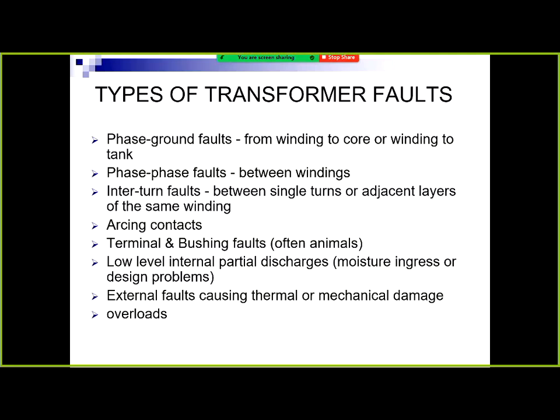So that would be arcing contacts. It's just sometimes you get a bad batch of contacts. I've heard that, and tap changers cause problems. They're arcing as they're moving over. So we have an argument with the manufacturer, we get them replaced, and who pays for the cost? They're what another group look after and argue about. So they're fairly common. We don't tend to get internal faults in the transformers very much, would be what I've heard. Overload, no, we tend to take care of that, watching it as an issue.